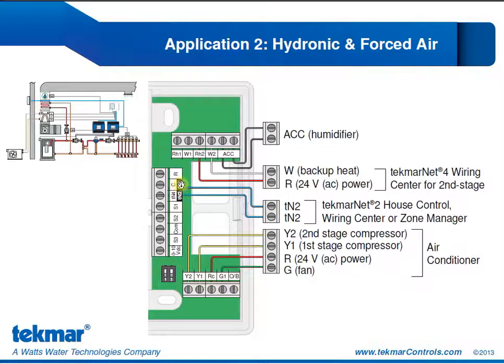Taking a closer look at the wiring. Because we're going to be connecting to a house control for that radiant heat operation, we're going to connect the TN2 terminals over to our house control. And so that first stage of heat is going to be communicated through the TN2. Notice there are no wires at RH1 or W1 because that first stage is all communicated through the TN2.